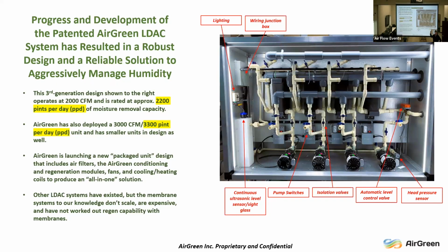This was a little more complicated because this is actually a photo from our pilot plant. This particular conditioning unit or dehumidifier has a double set of pipes, because we can take either a chilled water source in, or we can take refrigerated desiccant in. Out of the exit side of the pump, you'll see two legs there, and you'll see two feed and return lines. But we do some neat things here.